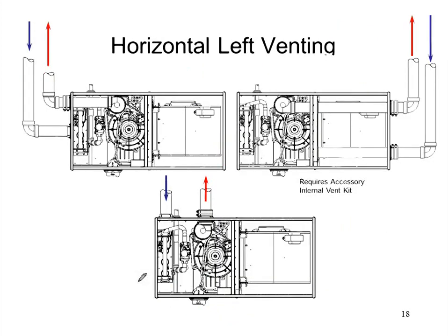I can also vent this horizontally to the left or horizontally to the right, and I can have my vent pipes coming out the top, which is now the left, the right, which is now the top, if you will, or I can have them venting out through the blower housing if I get that internal vent kit, and I would avoid doing this unless there's no other way to vent it out.